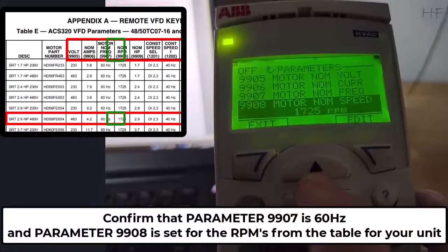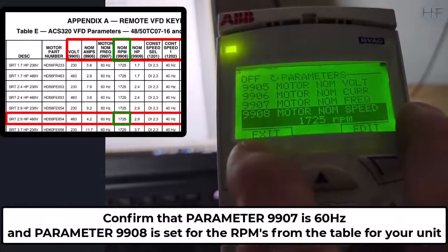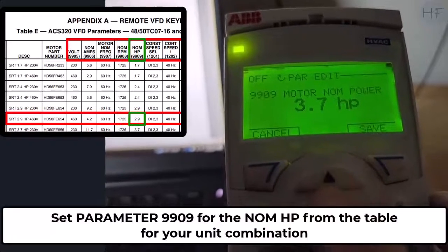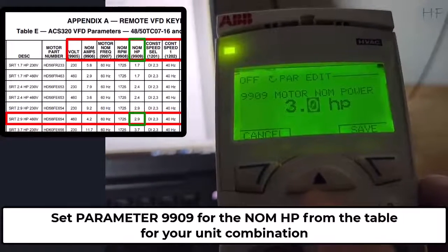Then verify that parameter 9907 is 60Hz and parameter 9908 is the value in the table. Set parameter 9909 for the horsepower rating of your motor.